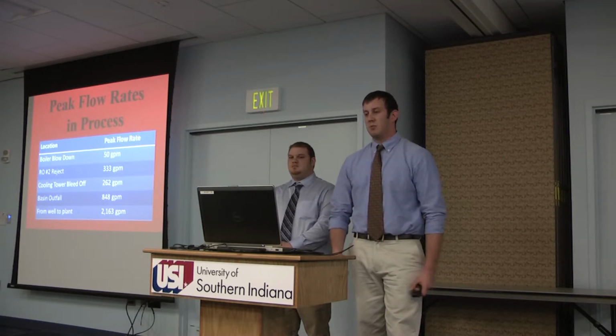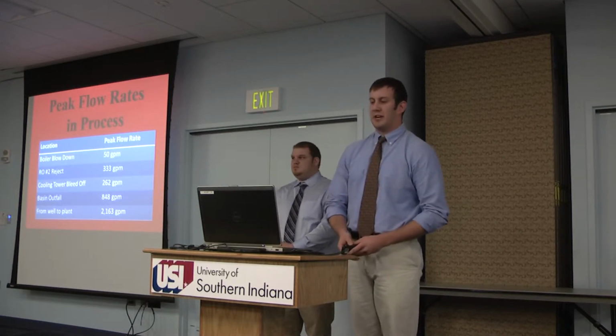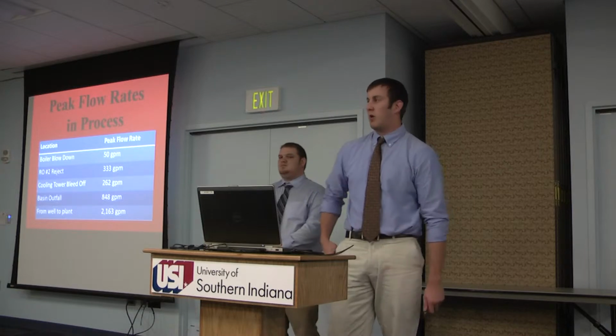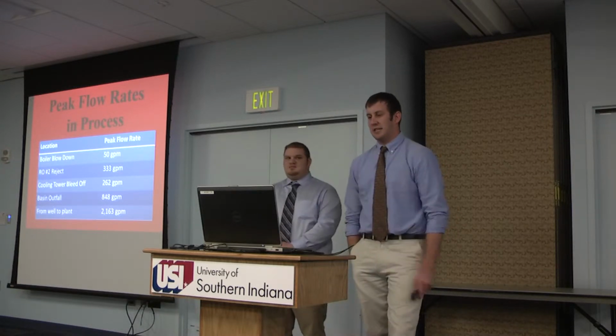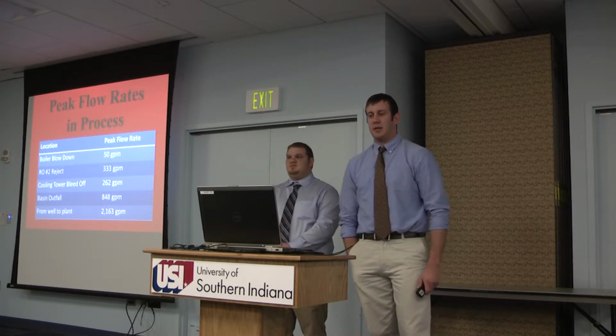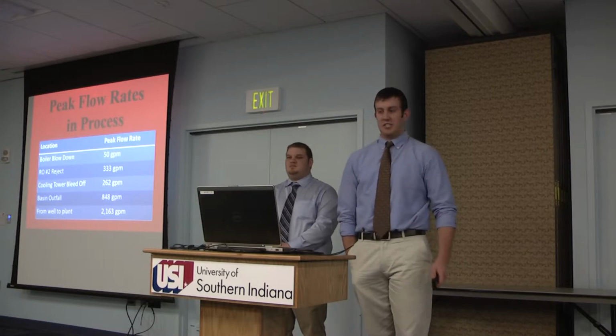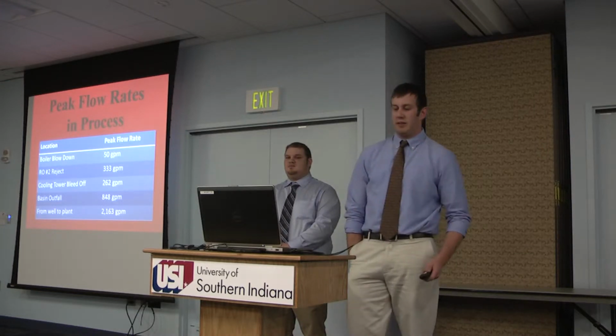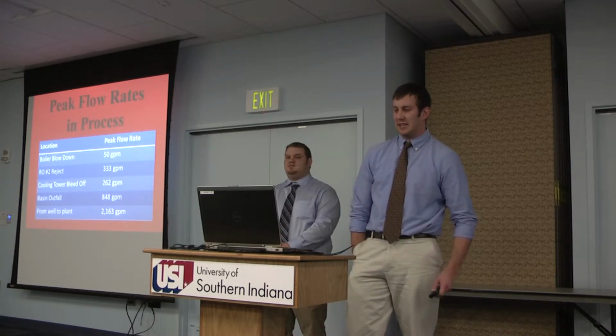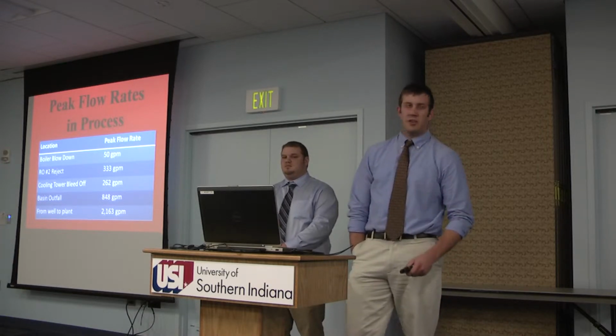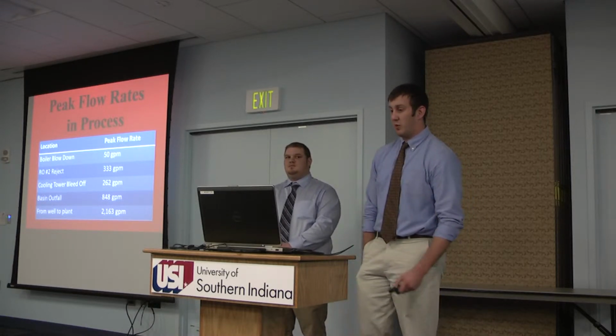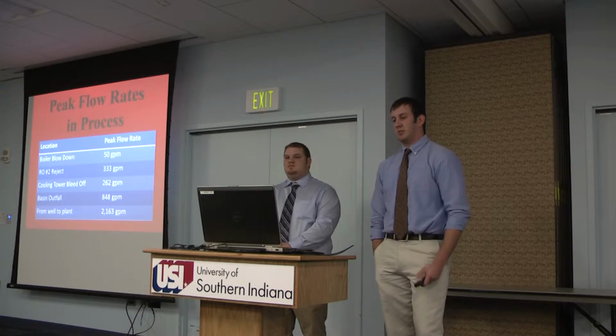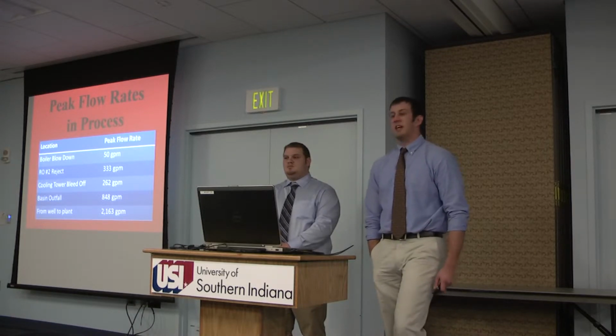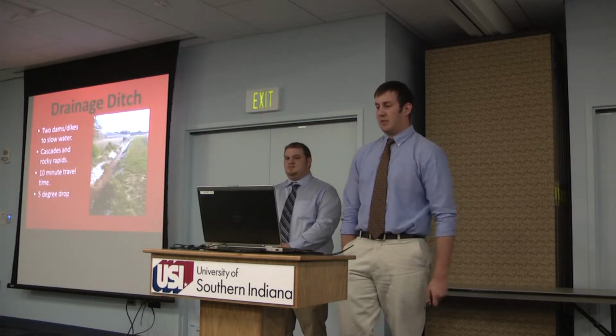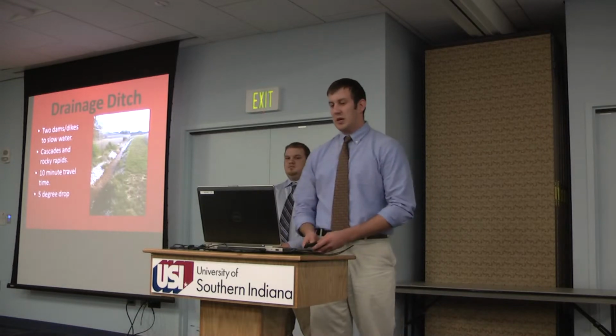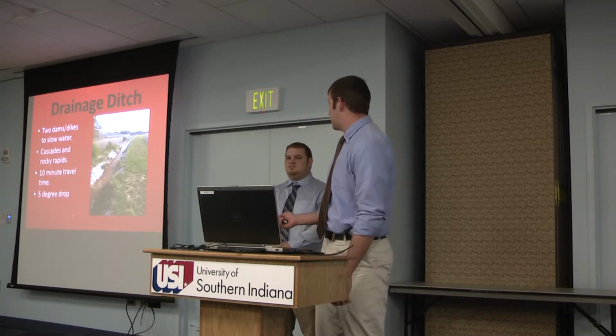The peak flow processes are: your boiler blowdowns at 50 gallons per minute, the RO blowdown reject at 333 gallons per minute, and the cooling tower bleed offs at 262 gallons per minute. And then the peak flow rate out of the basin is 848 gallons per minute. Also, the water coming to the plant from the well at about 55 degrees is roughly just under 2,200 gallons per minute. The drainage ditch, like I said before, is just for cooling.